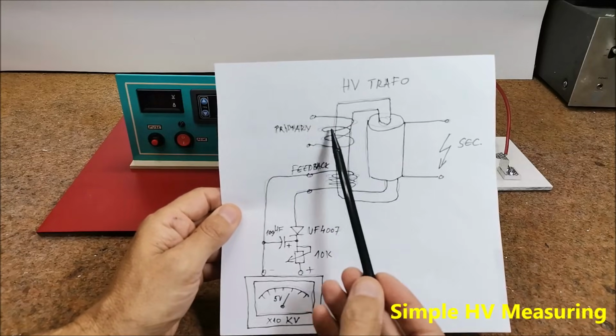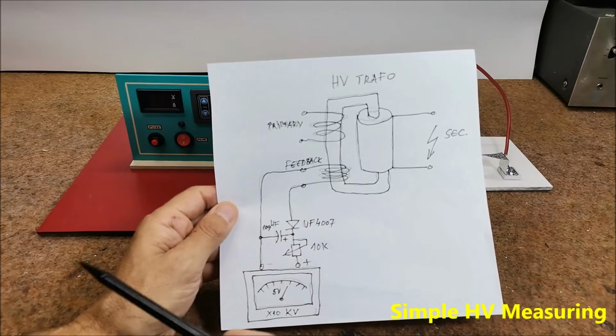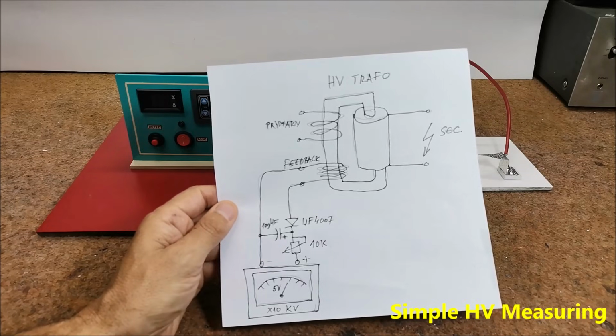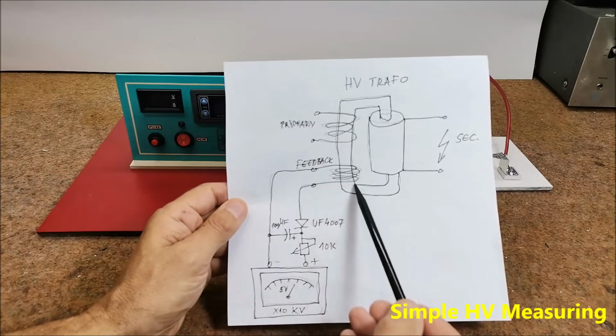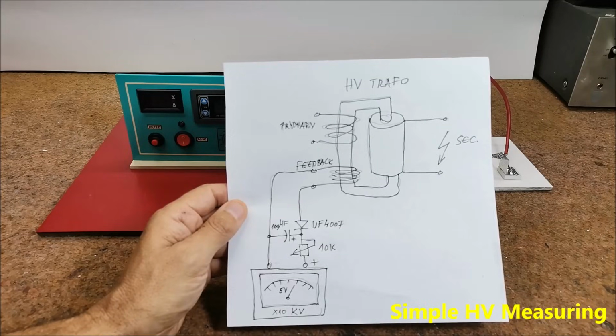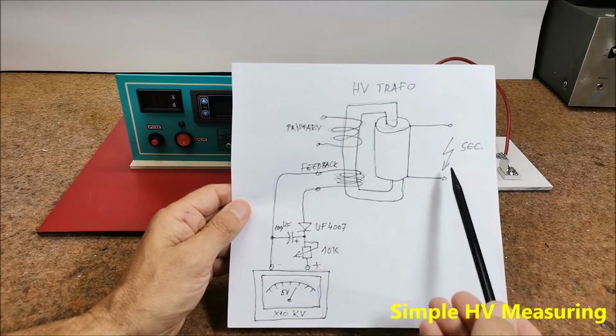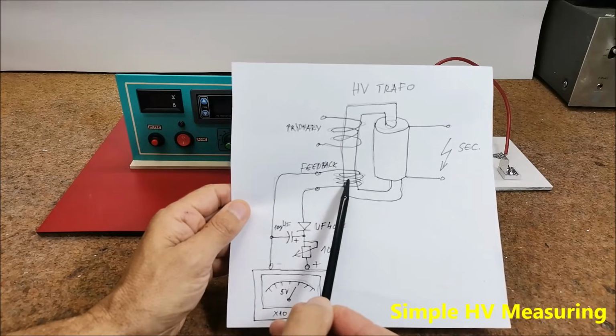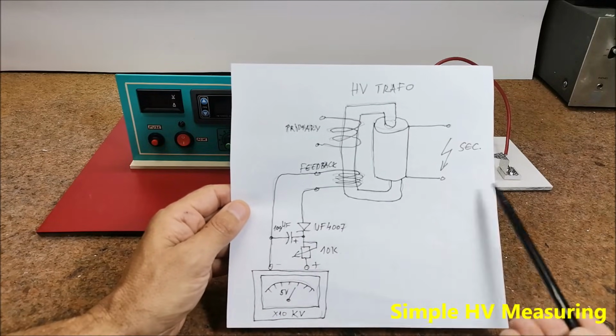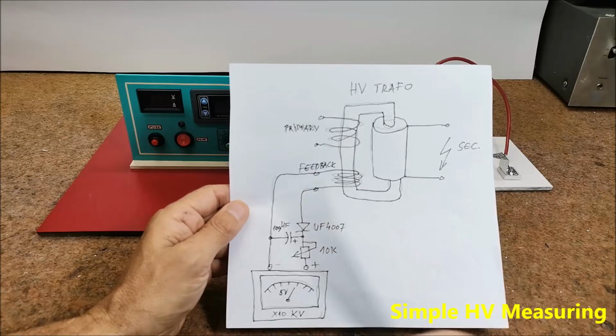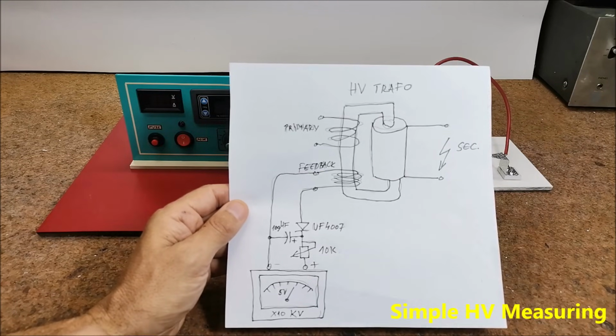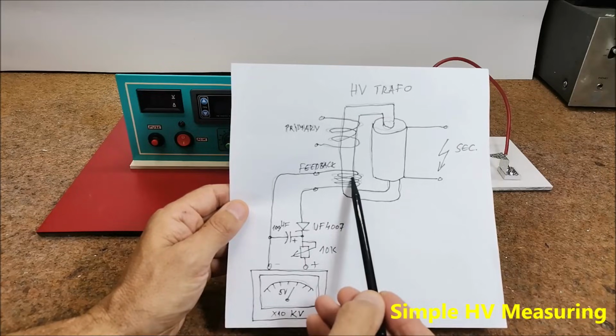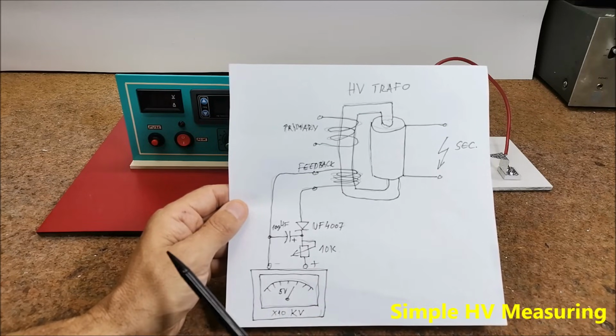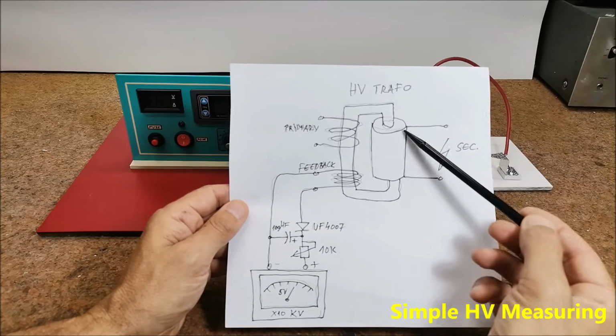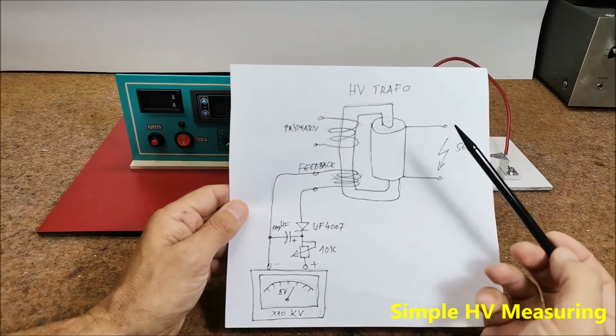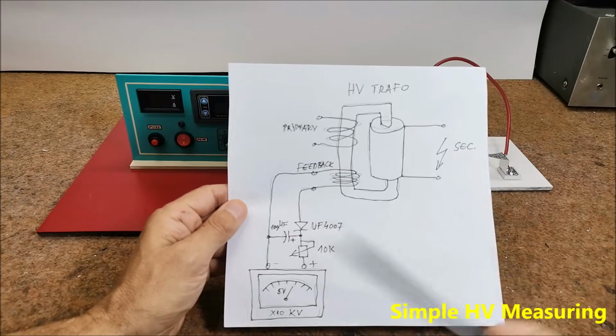The original primary windings, when working, creates a magnetic flux through the core, whereby the voltage induced in the secondary winding and this additional feedback winding is proportional to the strength of the magnetic flux. In this way, by measuring the voltage generated on the feedback windings, we relatively accurately determine the voltage induced in the secondary winding, that is the high voltage.